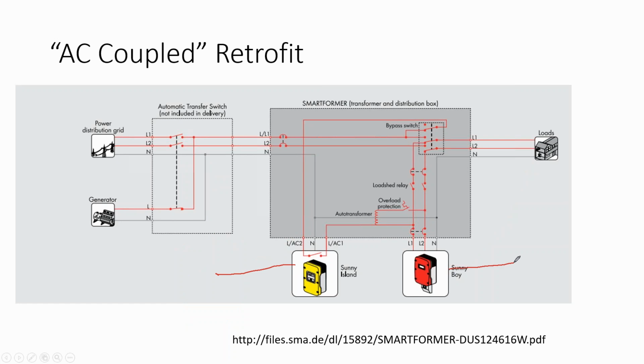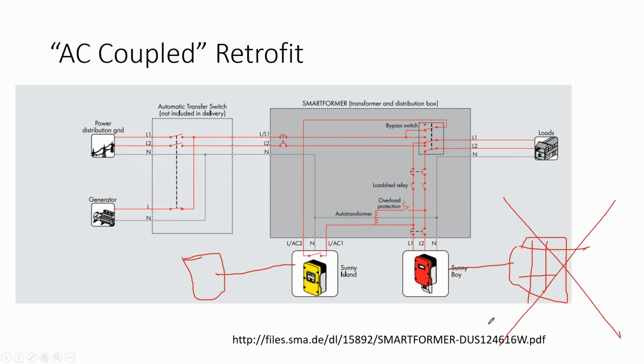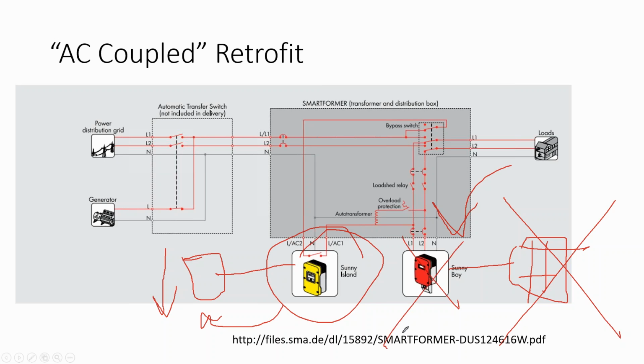But the problem with an AC coupled off-grid system is if my solar array is off because it's nighttime and my batteries fully drain down, my battery inverter can't turn on because my batteries are drained, and my solar array can't charge my batteries because it's off.